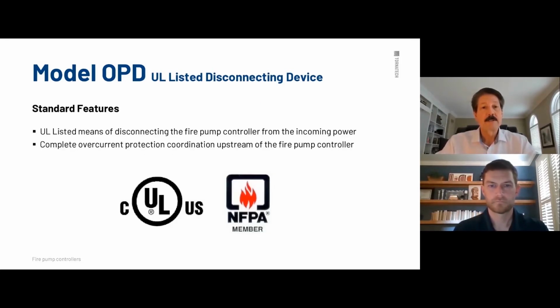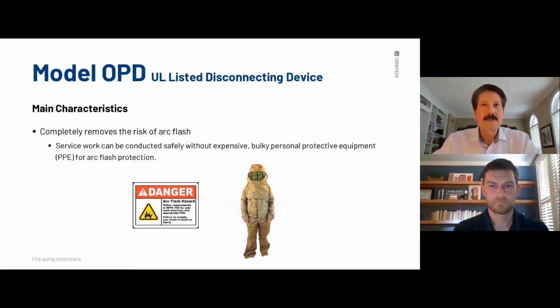Again, you see UL listed disconnecting means for fire pump controller from the incoming power. The key reason you do this is that when you have a main disconnect, and again, I'll mention fusible, I'll mention the OPD, and my preference would be OPD because it's more compact, more competitive, streamlined, and you don't blow a fuse and have to replace it. But again, one of the main reasons is that when you cut power off to a fire pump controller and you need to do any kind of servicing or even opening the door, if you don't have a main disconnect ahead of your fire pump controller and it's hardwired direct to the secondary of the transformer from the utility, when you open that door, even though you have the power off on the fire pump controller, you still have 3 cables coming into the isolation switch itself that are hot from the utility. That is arc flash potential.